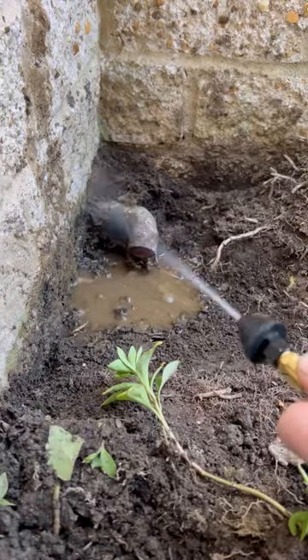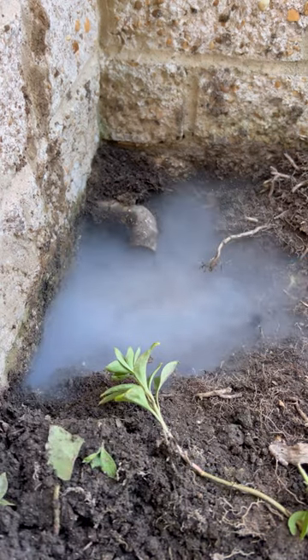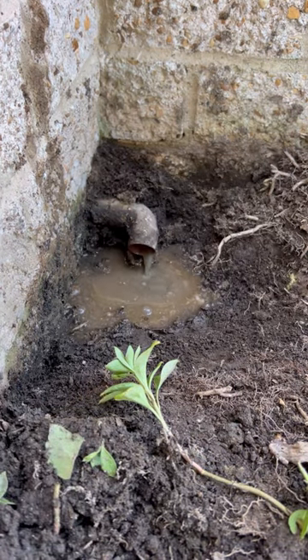I've got a clogged condensate line here, so I'm going to try to hit it with the swoosh gun from the outside. I thought the clog was very close to the outside. I was very careful not to shoot too much air and make a mess inside.